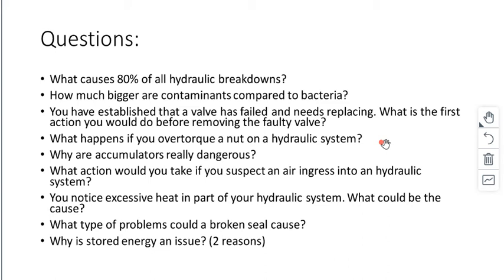You notice excessive heat in part of your hydraulic system. What could be the cause? Okay, something might be faulty. There's some sort of resistance. When you put energy into a system and there's a resistance to overcome, so it could be a leak of some sort or another, heat is generated as a byproduct. Yeah. So if the energy cannot be translated into torque, for example, like an hydraulic motor, it'll turn into heat. Basically, it's a problem. Yeah.